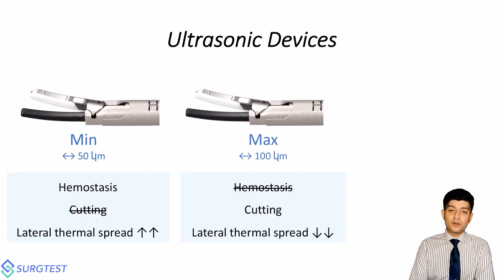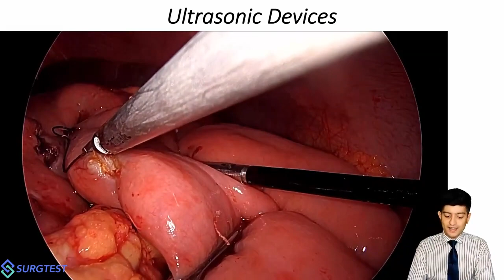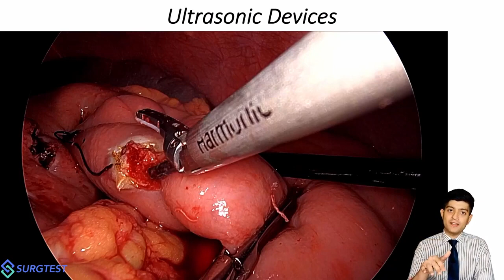Ultrasonic devices have all sorts of uses in surgery. This is me using it to create an enterotomy. You can see the vapor that is coming out from use. The tissues do not have any eschar. Now I'm going to use the active blade to essentially penetrate across, using it like a scalpel, if you may, to create an enterotomy in this case. So you can always use the active blade to just hold up tissues and fire the blade to cause some amount of division, or to enter tissue planes, the active blade can be used with the jaw open.